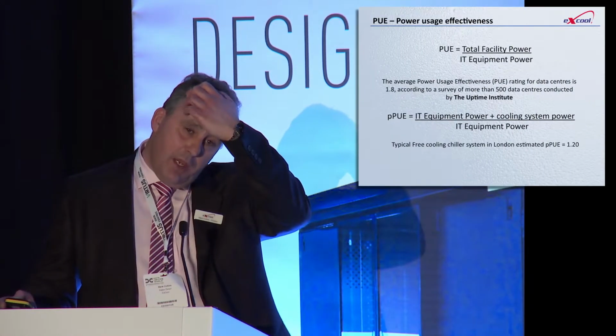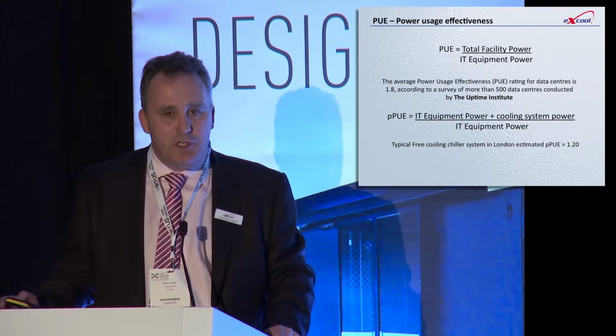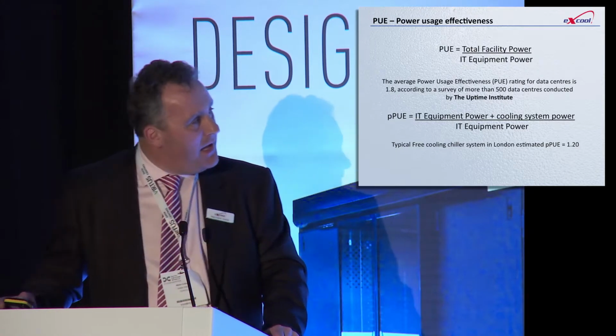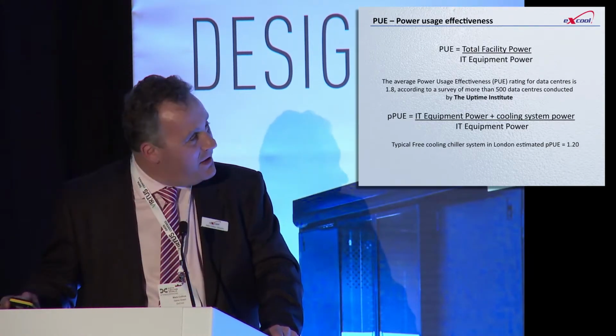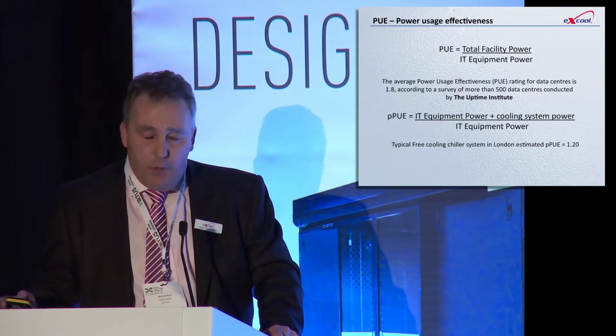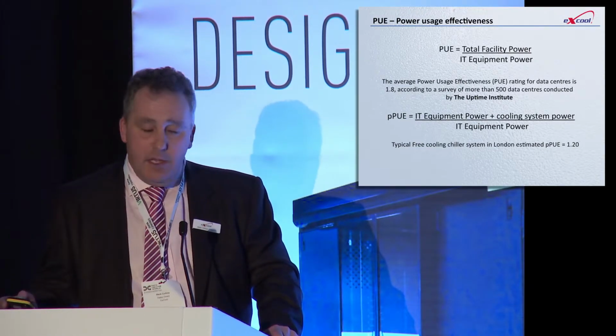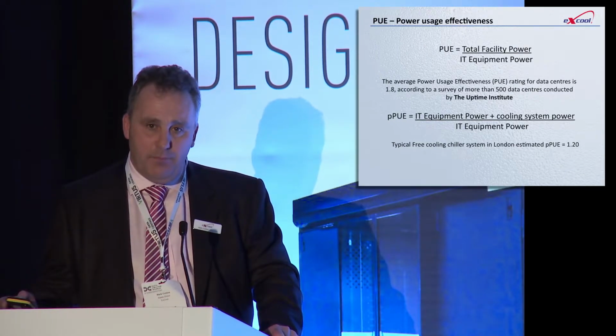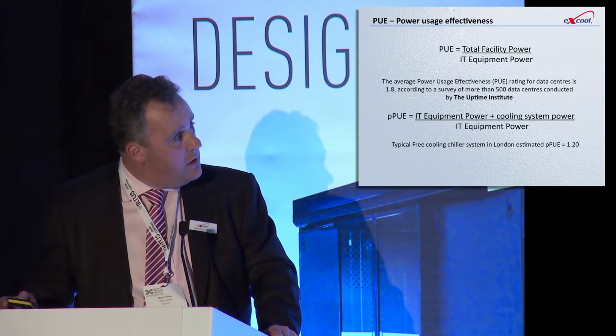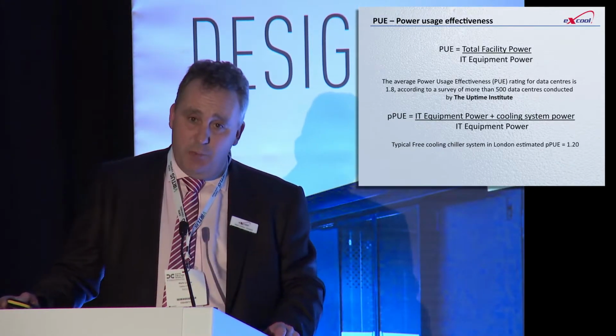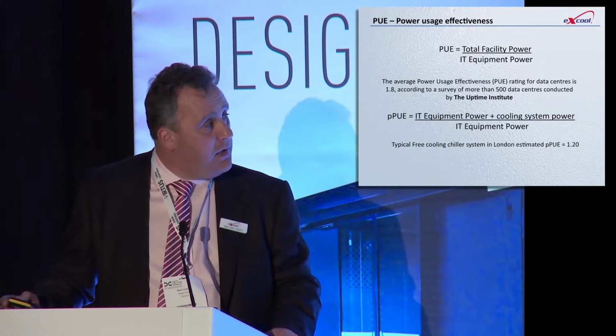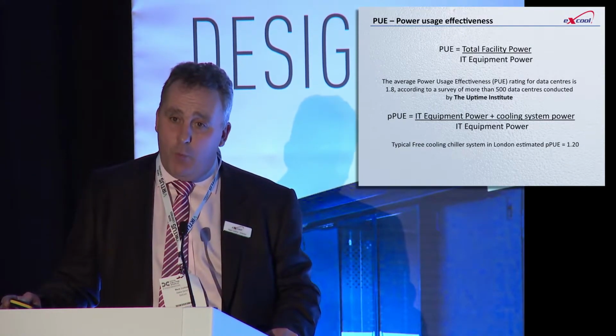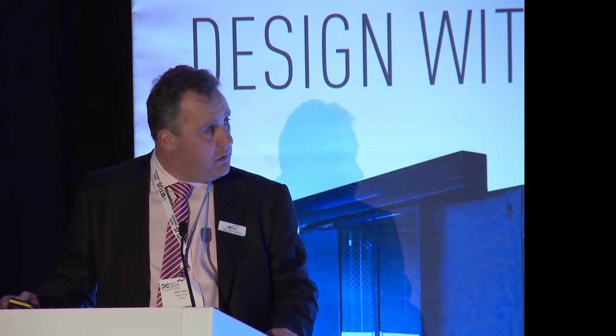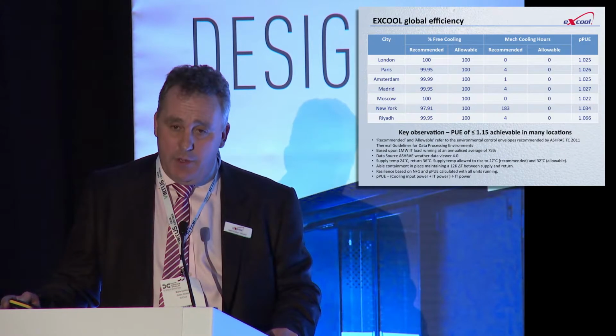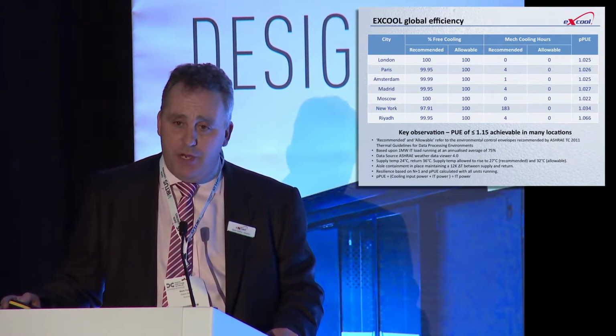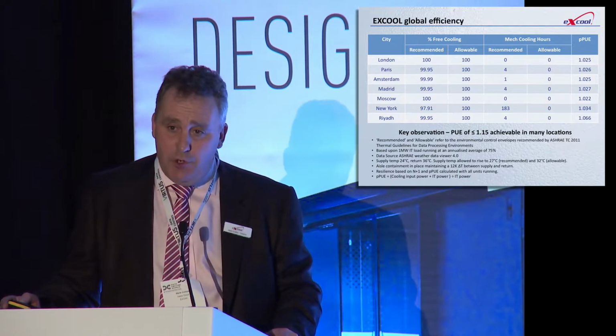So I want to talk about PUEs. It's a pet hate of mine, but it's quite a useful metric to use, as most of you in this room will understand it. I think it's a bit flawed, but it's something that the whole industry understands. But what I want to talk about is partial PUE, so the PUE that applies only to the cooling section of the calculation. And typically with a free cooling chiller system, which is the system of choice up until very recently, a chiller system would have a partial PUE at best of around 1.2. These are the sort of PUE levels that we get with Excool. So we're down at around 1.03 or lower throughout most of Europe.